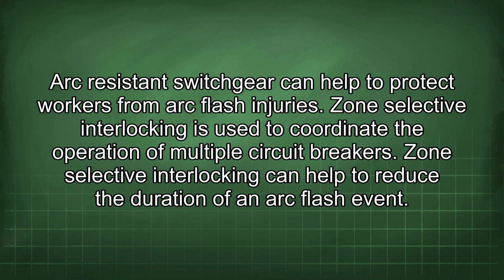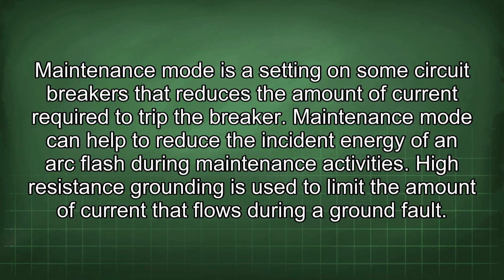Zone-selective interlocking is used to coordinate the operation of multiple circuit breakers. Zone-selective interlocking can help to reduce the duration of an arc flash event. Maintenance mode is a setting on some circuit breakers that reduces the amount of current required to trip the breaker. Maintenance mode can help to reduce the incident energy of an arc flash during maintenance activities.